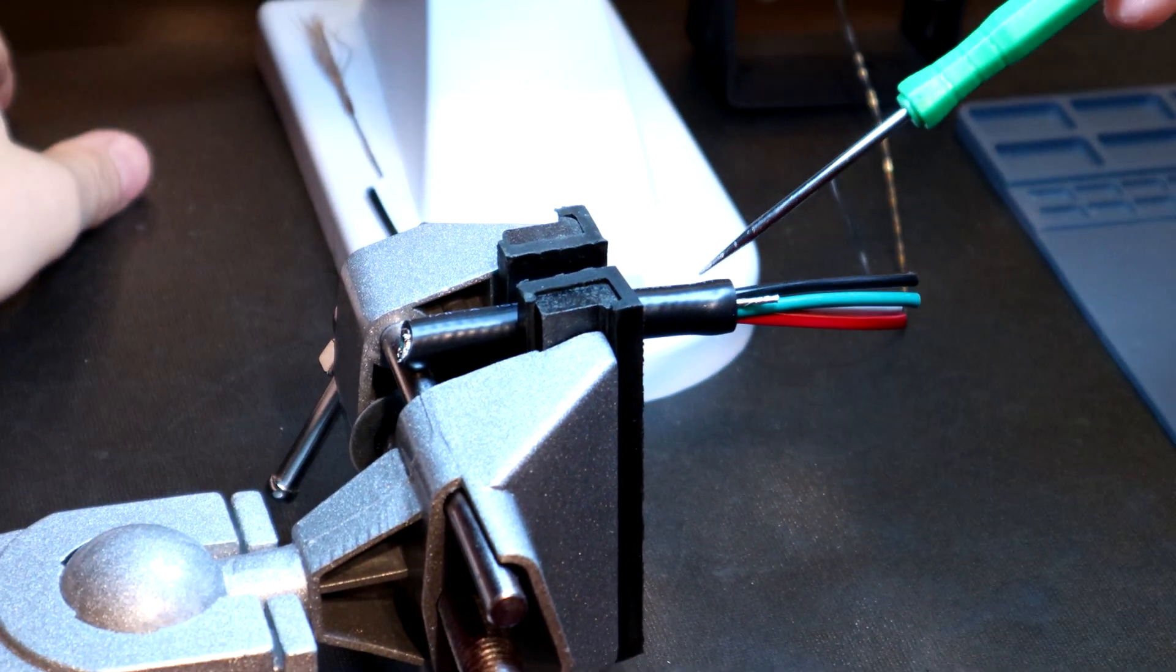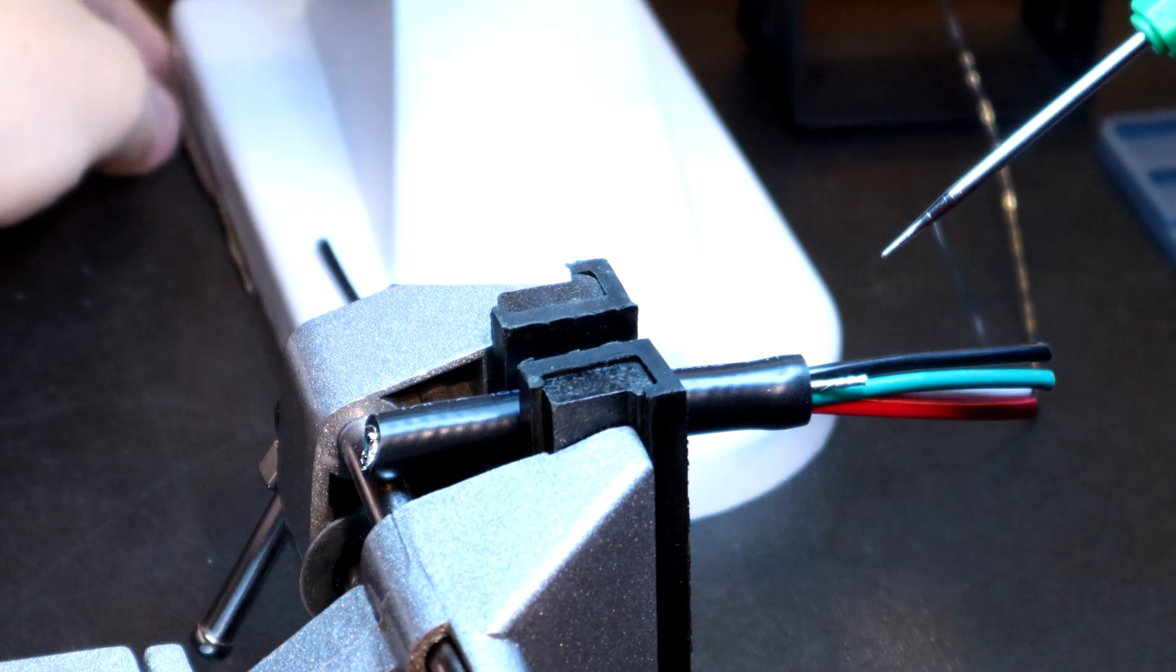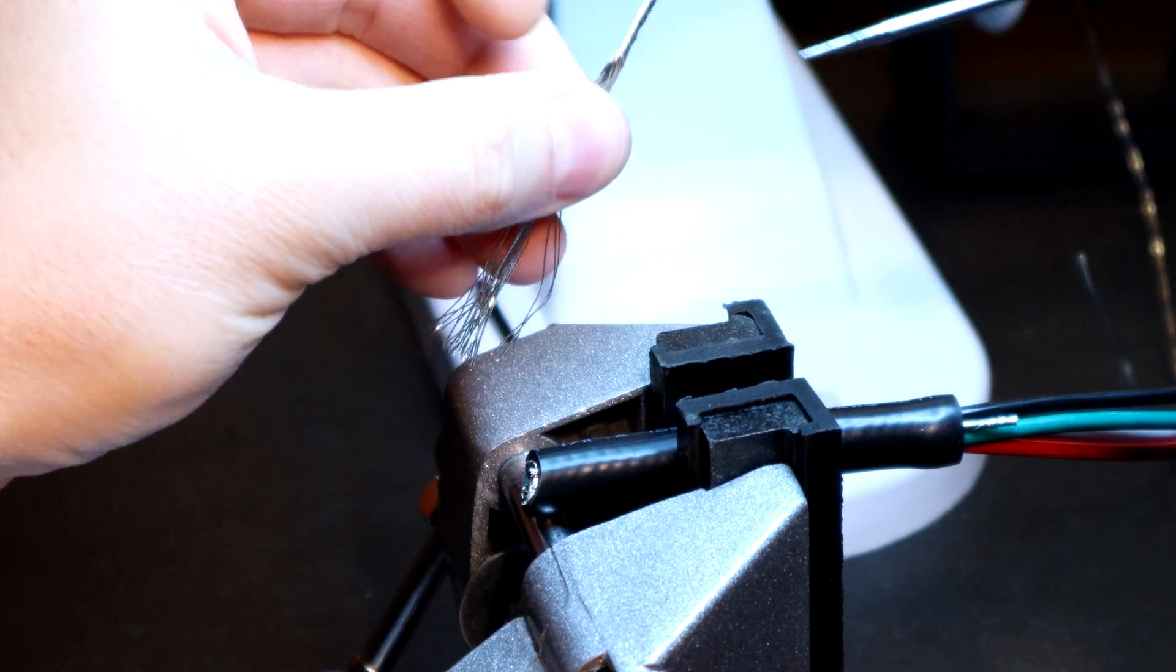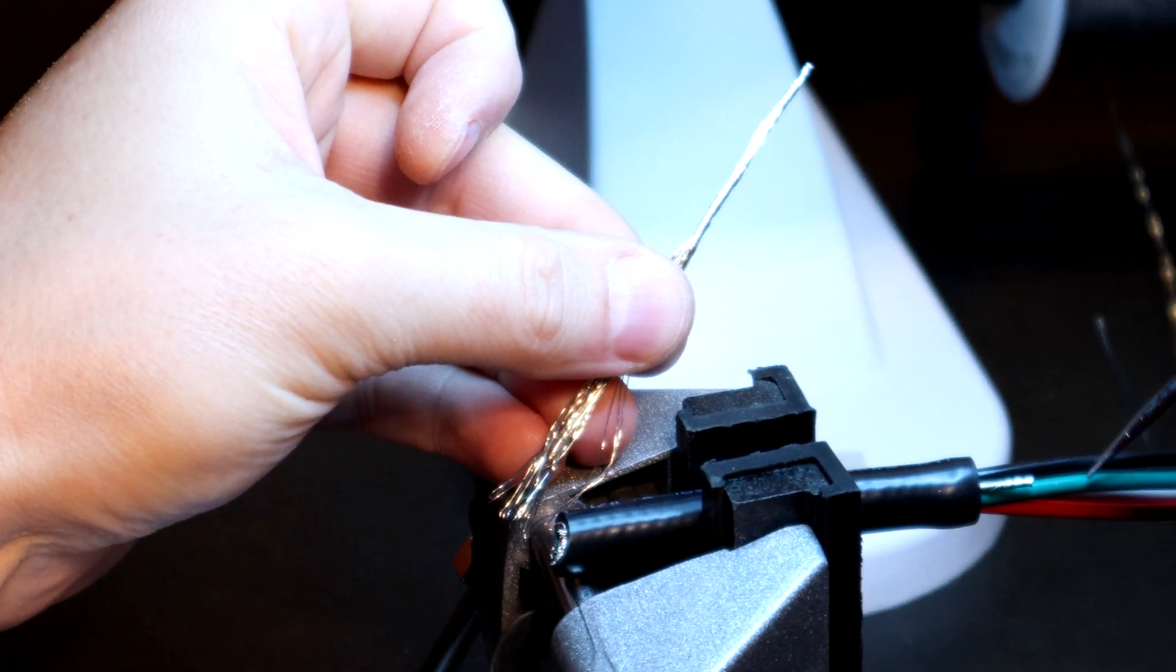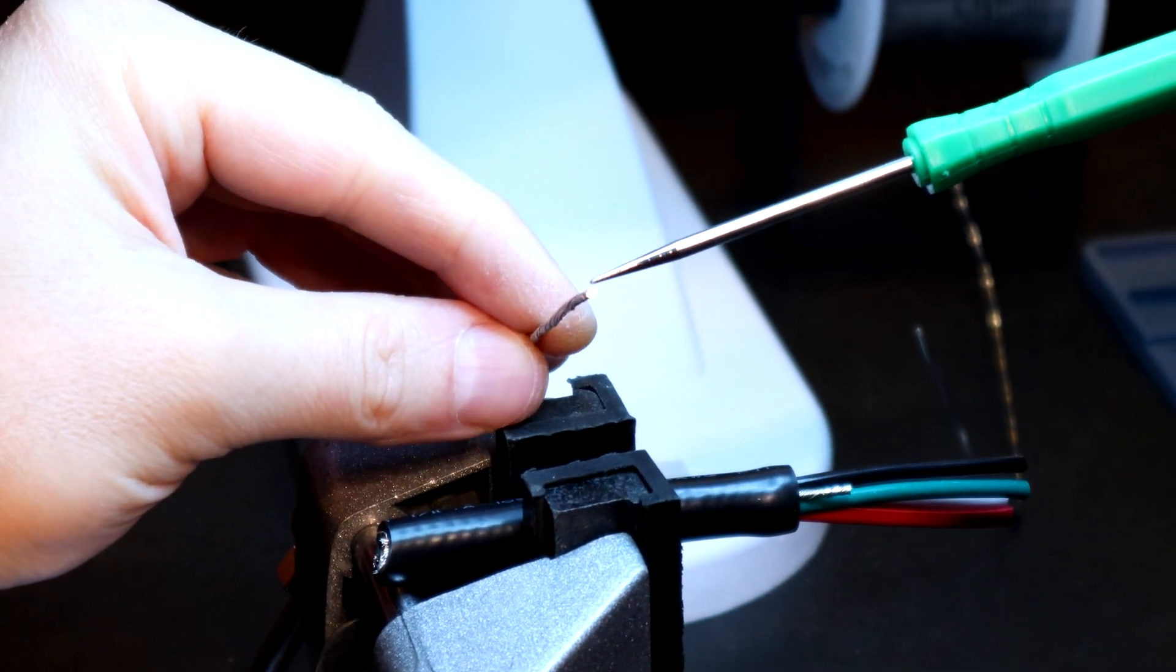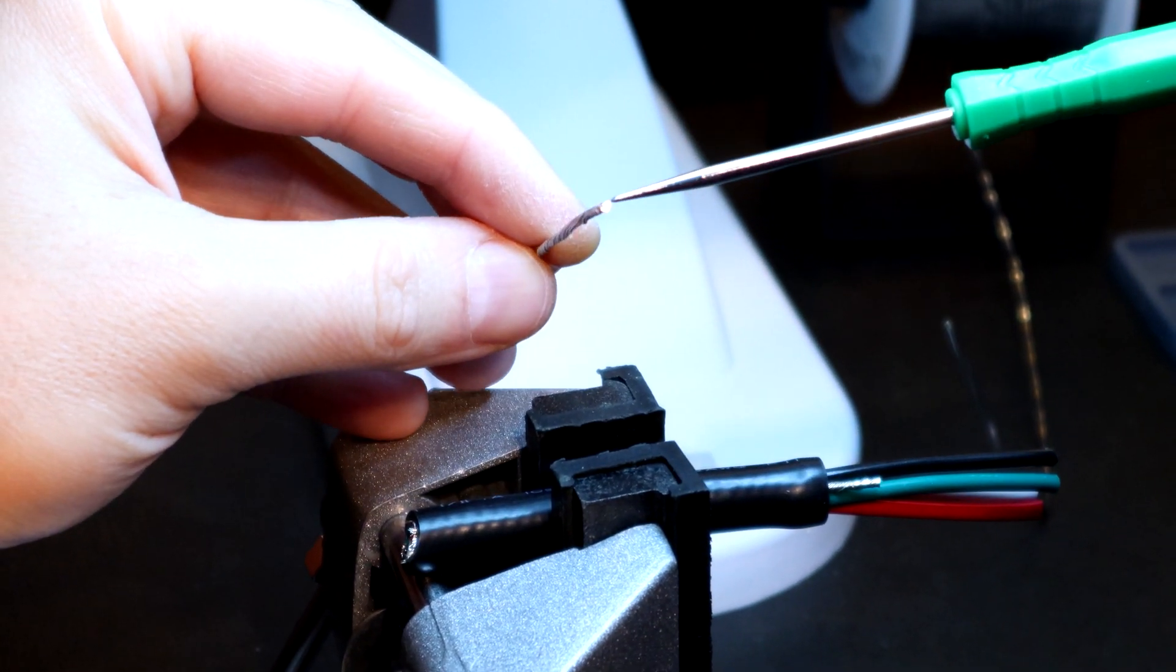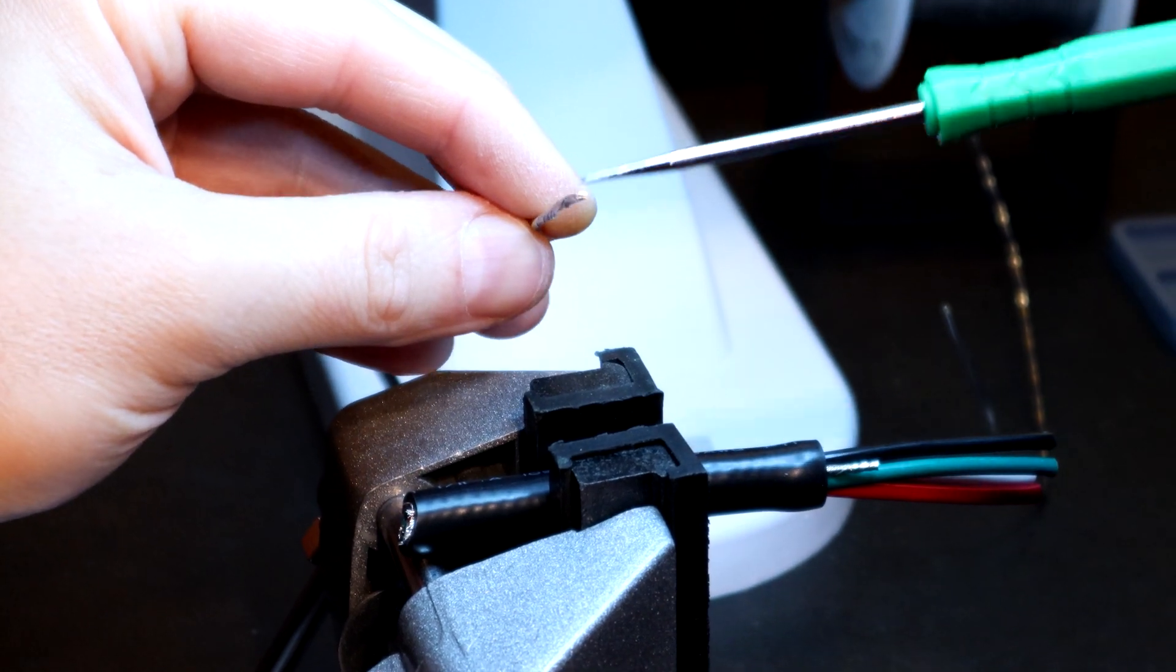So, what I've got here, once again, is my 16-4 double shielded cable. Shield drain is pre-tinned. Now, I actually have a shield drain from my cable. It is 16 gauge. The shield drain is the same gauge as the actual conductors inside the cable. And what you'll notice is, when this is properly soldered, you will see that all conductors become one, because the solder merges all the conductors, welds them all together, and that's what you should see.